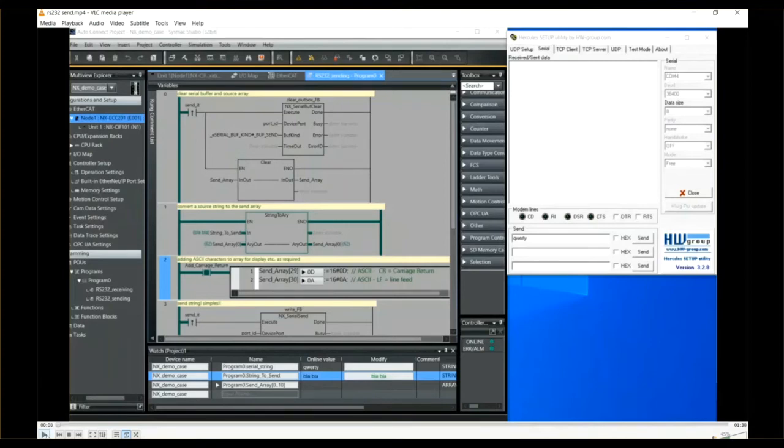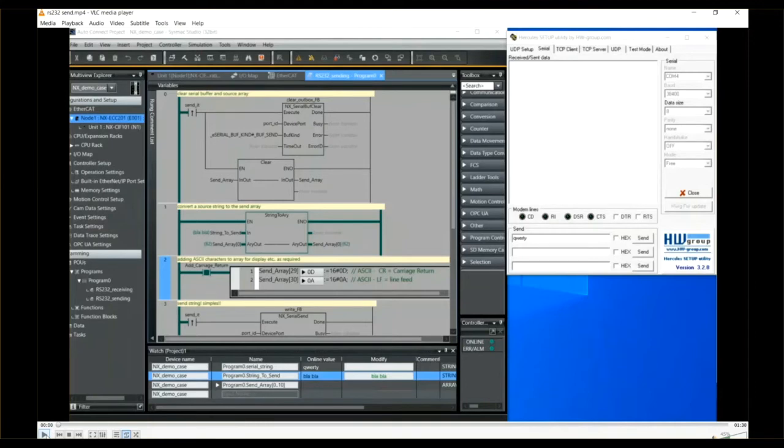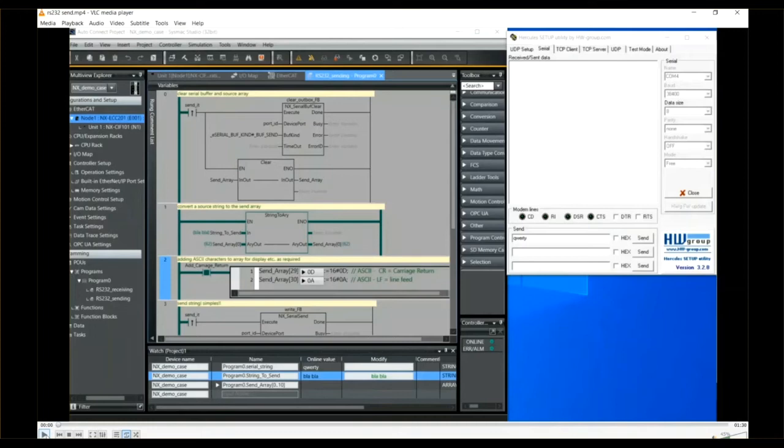The sending program, as you can see on the screen now, needs only four rungs and uses two functions or function blocks: NX_SerialBufClear and the NX_SerialSend function block. With these two functions we can simply prepare an array of bytes to send.